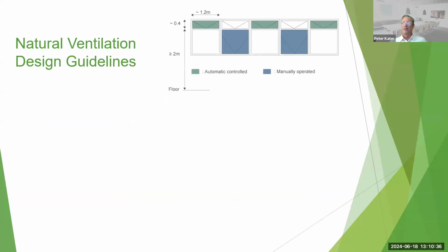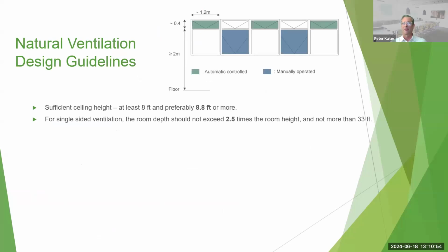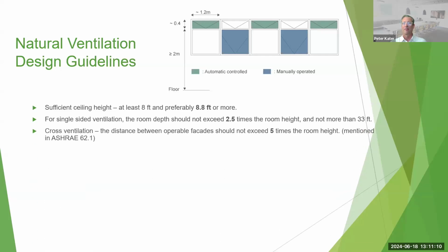Some basic design guidelines when you're thinking about including a natural ventilation system in your building design. And these include a sufficient ceiling height, typically 8 feet or more is ideal, particularly for single-sided ventilation. The room depth with single-sided ventilation shouldn't be more than about 2.5 times the height of the ceiling, and never more than about 30 feet to have a meaningful effect. Cross ventilation, the distance between the operable windows on each elevation shouldn't exceed about 5 times the height of the room.